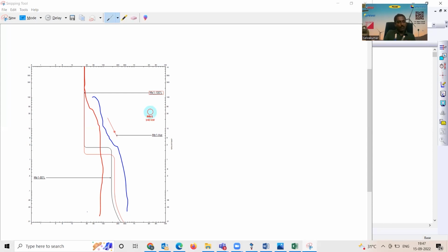We have quite a lot of examples. In one of the projects in Qatar, during energization, the motor tripped 30 times. The customer had adjusted the setting, probably some other consultant had given it, and he modified the setting at site and tried again, and after 30 attempts he understood it is not trial and error, it's a science. So then he came to us and we provided a solution.